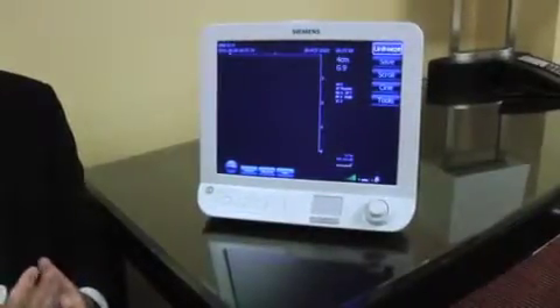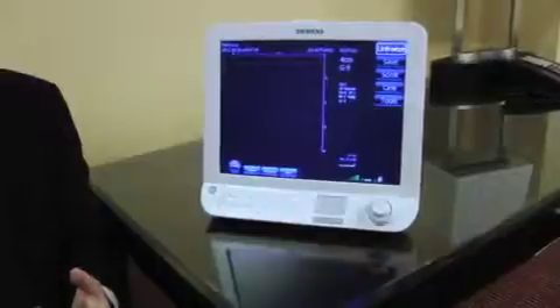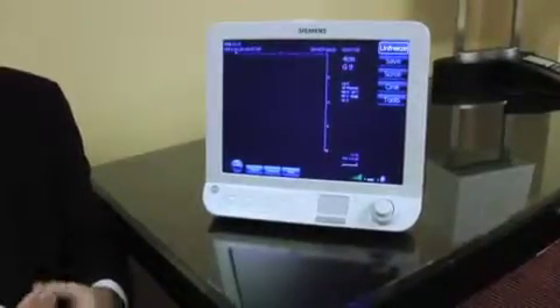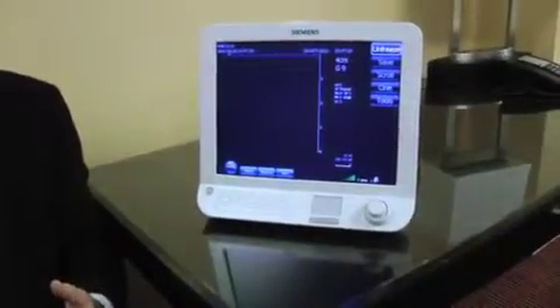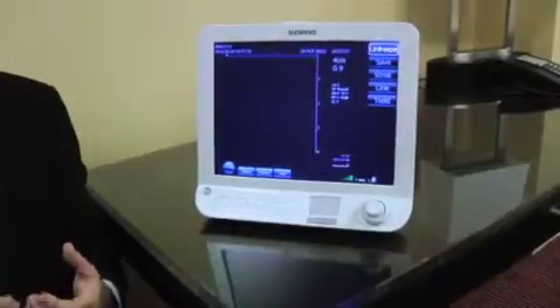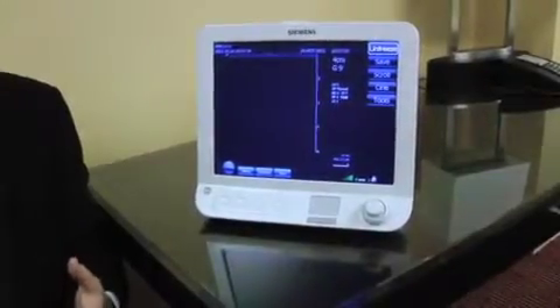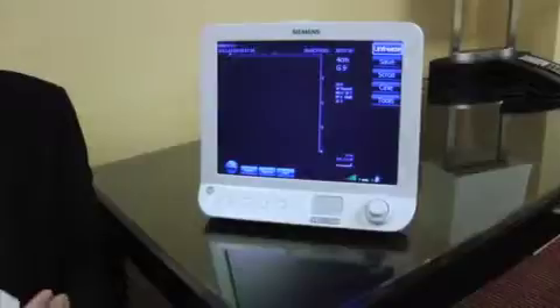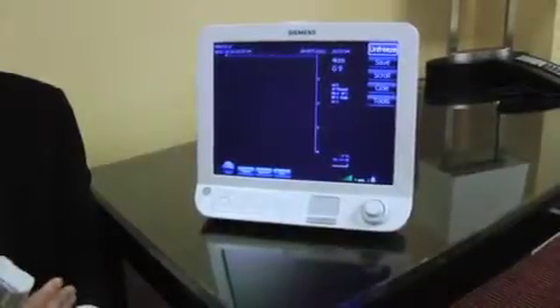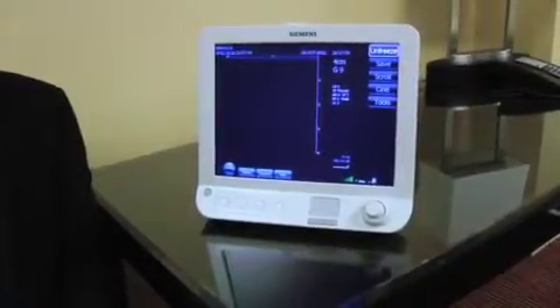Another important part of the design is that we have a large high-resolution display with LED technology, which gives you a very bright image, which is critical for this use because unlike a lot of conventional ultrasound, the scanning is typically done in a room with very bright lights on. And so we designed the image quality and the processing and the presentation to take into account that this is often done in a room where you do not have the ability to lower the lights.